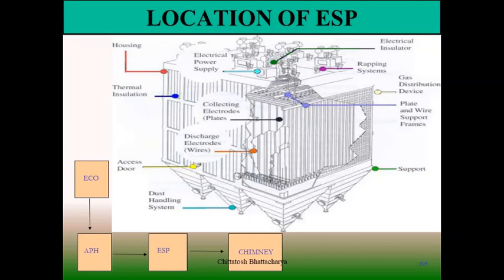When the gas flows through the system, the particles are charged by the emitting electrodes and the charged particles accumulate on the collecting plates. There is a DC power supply and rapping system available. The rapping system dislodges the collected ash to the bottom hoppers, from where it is disposed to the conveyor system to the ash handling plant. The outside of the ESP is totally insulated so that temperature can be maintained and there is no accumulation or sticking of ash particles within the collecting plates.